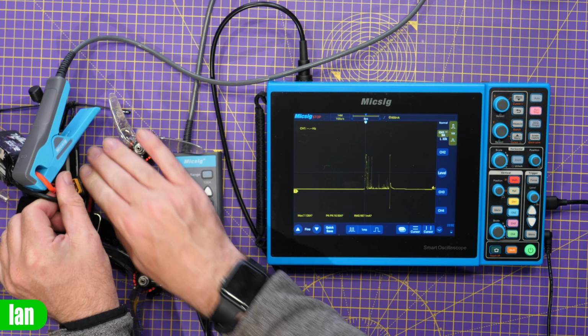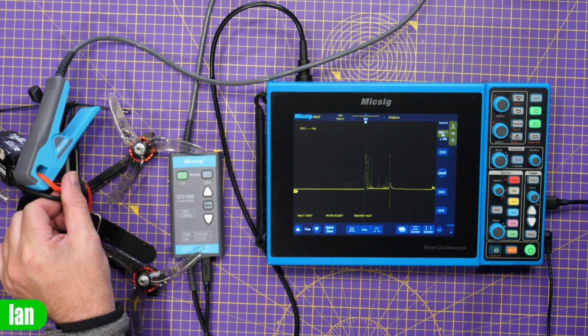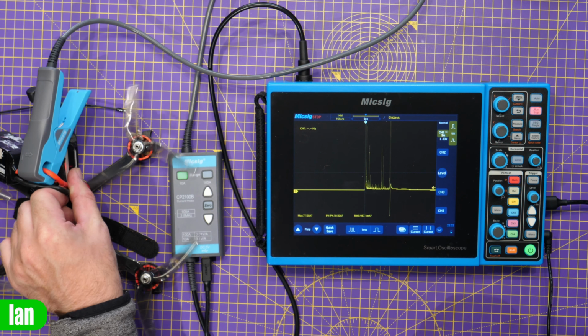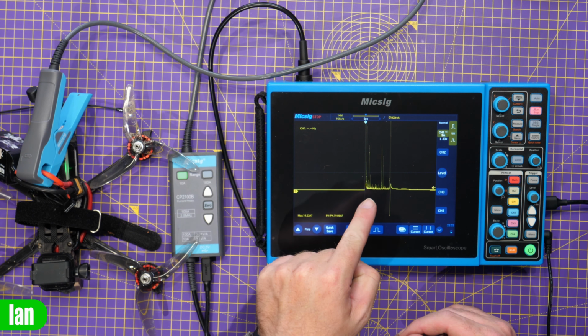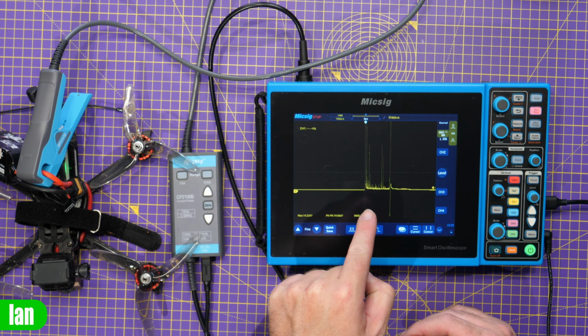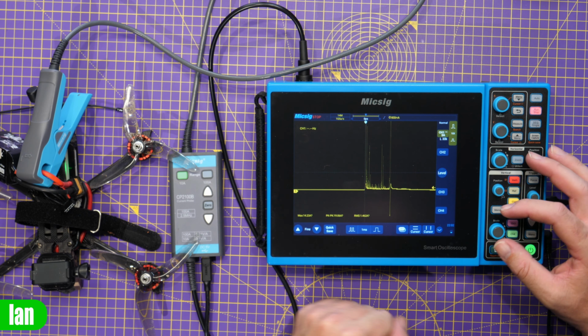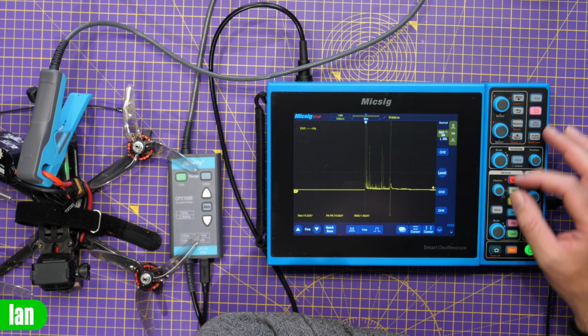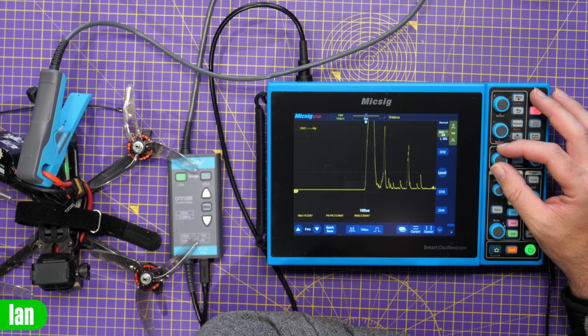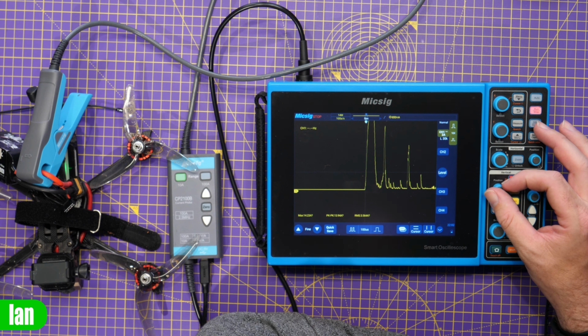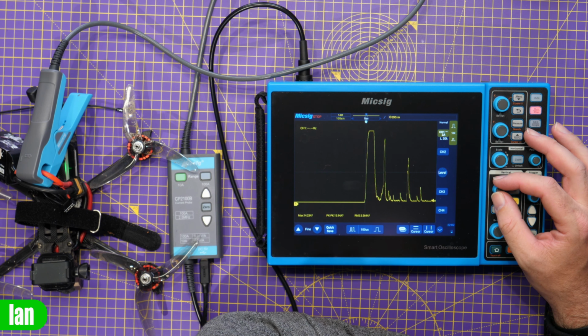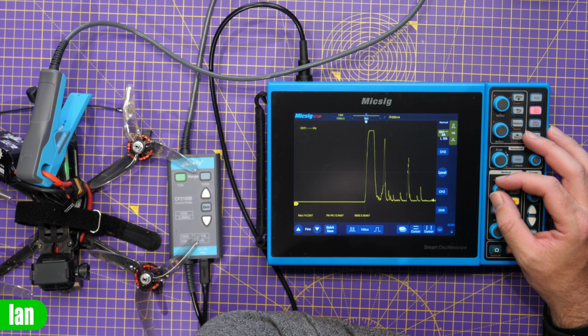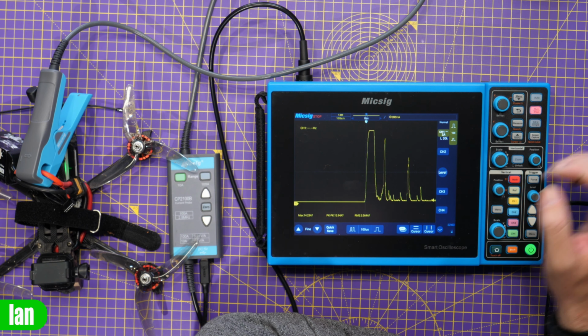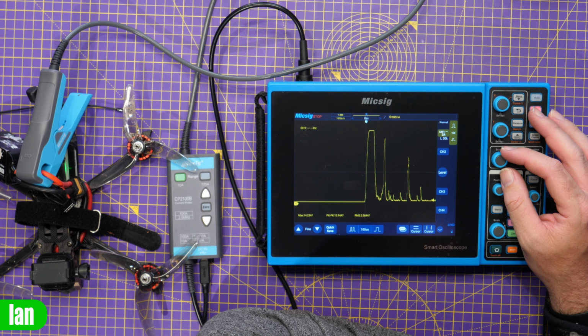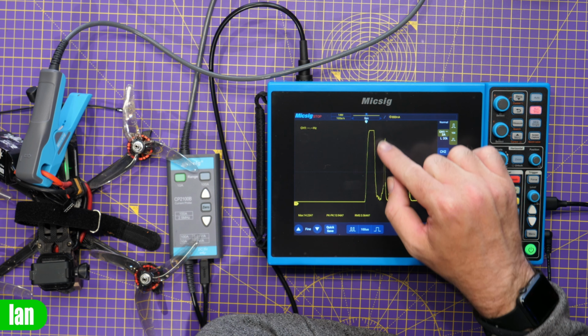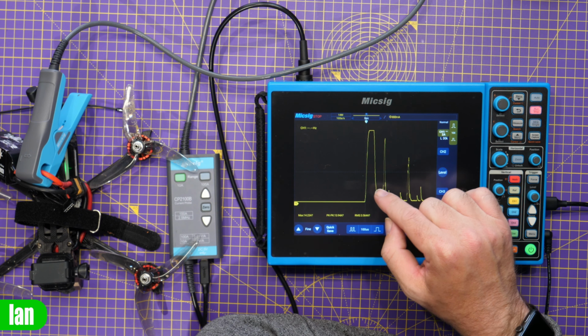So what we'll do is we'll just unplug the quad, we'll set it to single mode, which clears the display, and then we'll go in, and you can see instantly that massive inrush current that was visible on the input. Now, if we zoom in to take a look at this, so what we can do is zoom into the scale, and you can see the point that nothing came in. And you can see at that point, there was a peak or a max of 14 amp in total. So that is a huge amount of current for a second as we connect up.